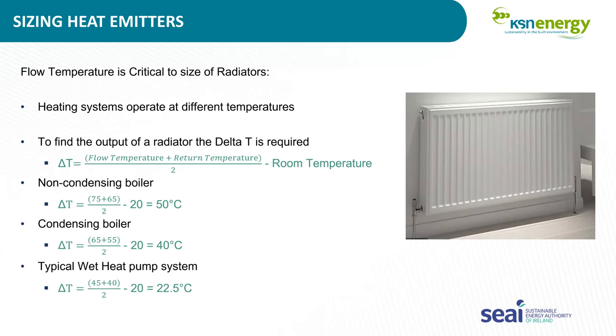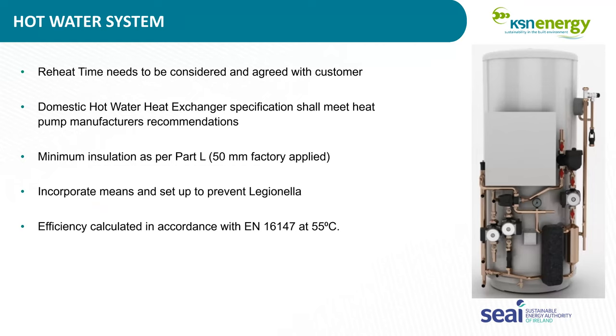But again, you can see when we look at a non-condensing boiler run at those temperatures, the delta T is 50 degrees, whereas with a typical heat pump system it's only 22.5 degrees. That's where it's very important that the radiators are sized adequately. The next thing is the hot water.